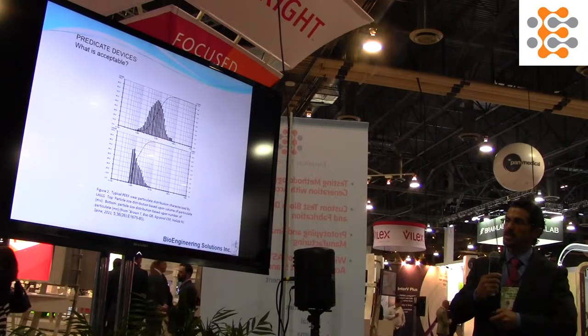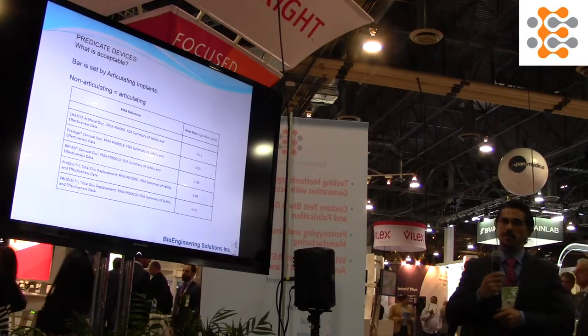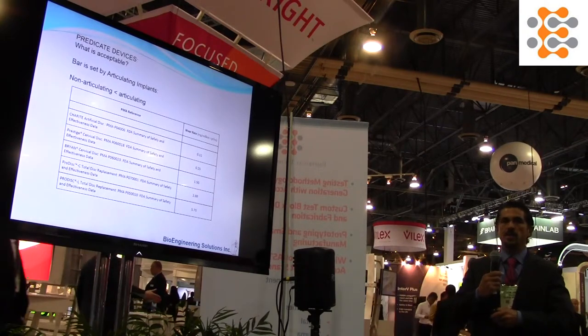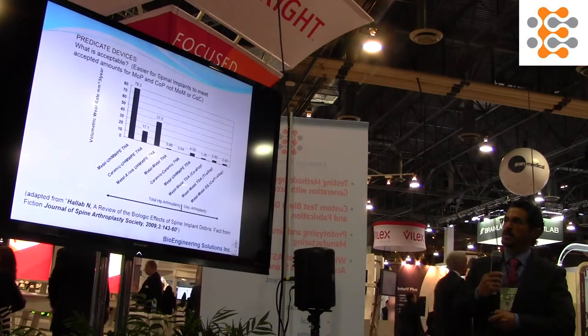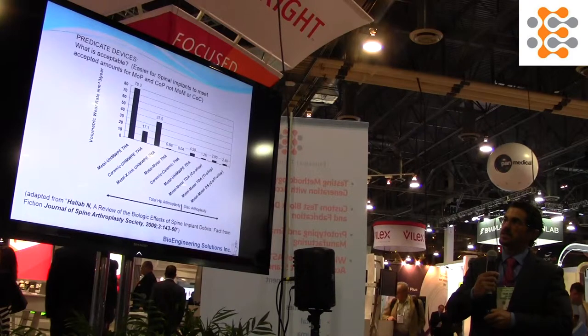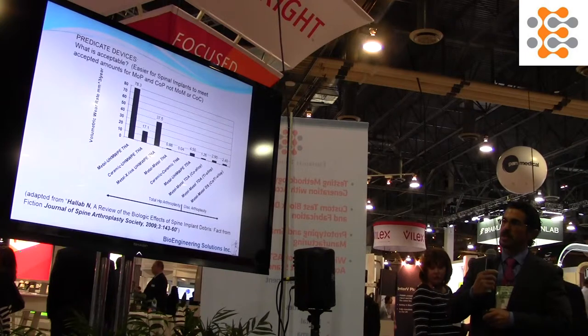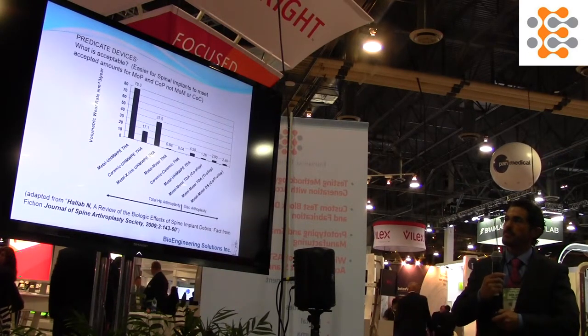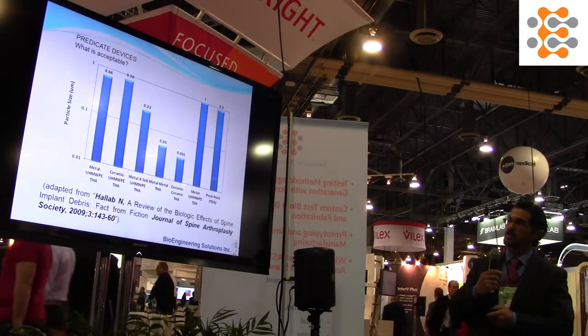What is acceptable criteria? There's a lot of data out there for different implants at the FDA website, and you can compare current implants to past implants when it comes to wear, particle size, and particle number. It's easier for spinal implants to meet accepted amounts for metal-on-poly and ceramic-on-poly because of the lower wear rates associated with spinal devices compared to hips and knees. What is acceptable from a particle size perspective is also available.